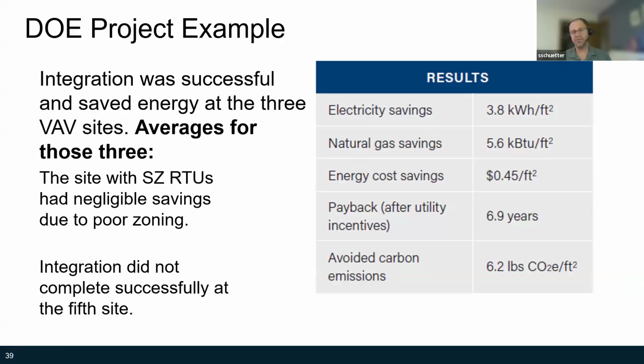Integration was successful and saved energy at the 3 VAV sites. The average electricity savings across these sites was 3.8 kilowatt hours per square foot. Natural gas savings averaged 5.6 kBTUs per square foot. And applying the electric rates at these sites to the energy savings resulted in utility bill reductions of 45 cents per square foot. Simple paybacks were calculated using capital costs and utility incentives and averaged approximately 7 years. The sites with single-zone rooftop units had negligible savings due to poor zoning, and integration was not completed at the 5th site.